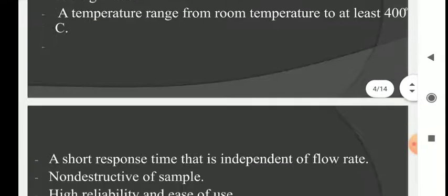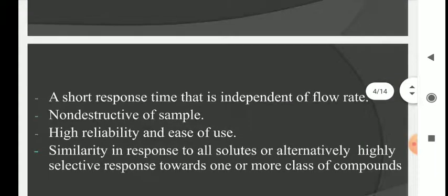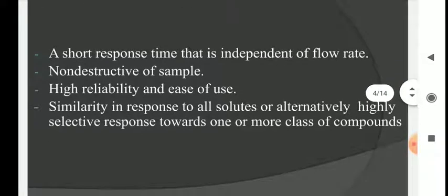Some of the other properties: the detector should have a short response time that is independent of the flow rate. Short response time means as soon as the components of the mixture reach the detector, it should give you a signal. It should not be like a tube light that takes time to light up. It should give the response immediately. As soon as the solutes come into the detector, you should get the signal. You should have a short response time.